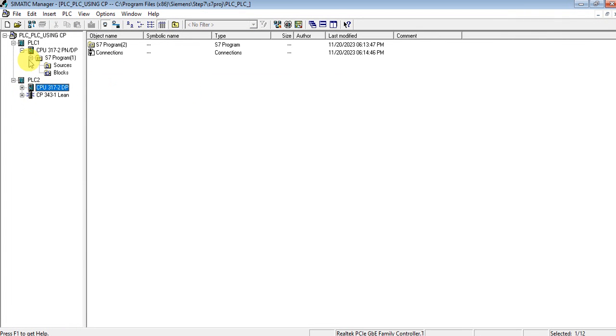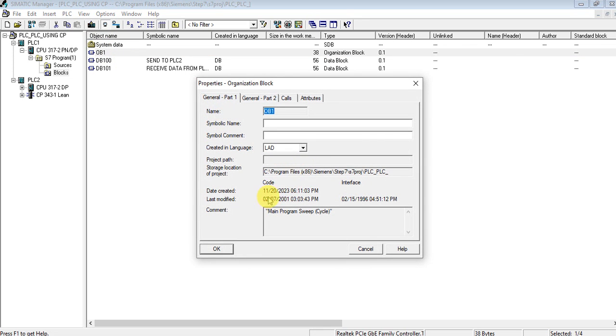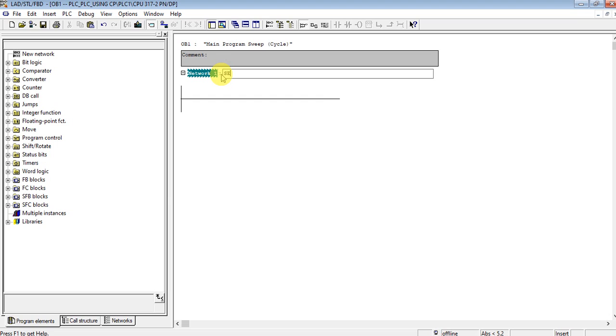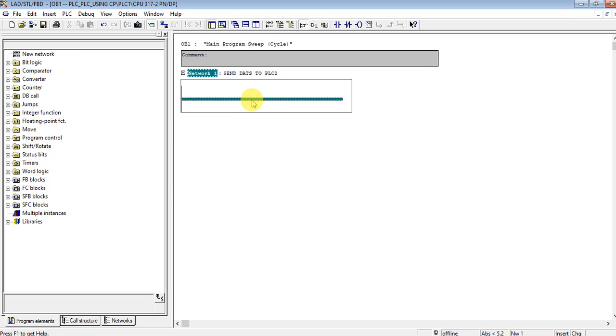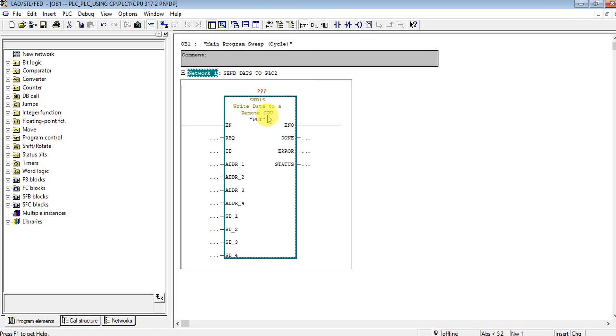The main advantage of PUT/GET is we can configure and program from one PLC. I can program on PLC1 to write to PLC2 and also read data from PLC2 — that's the main advantage. Let's open OB1. Let's send data to PLC2 using SFB 15 — that's the PUT instruction.